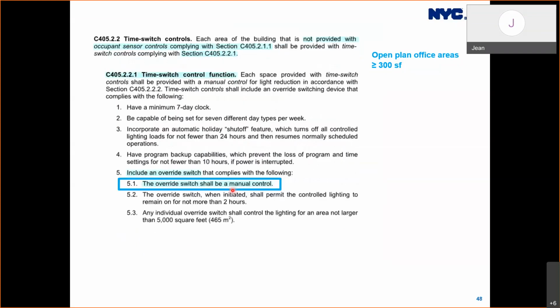But if you keep going down in the code, there is a C405.2.2, and it says the area not provided with occupancy controls complying with this section shall be provided with this time switch control function. And the open plan office areas of 300 square feet or greater falls into this category. So according to this section, these larger open plan office areas must have time switch control function.